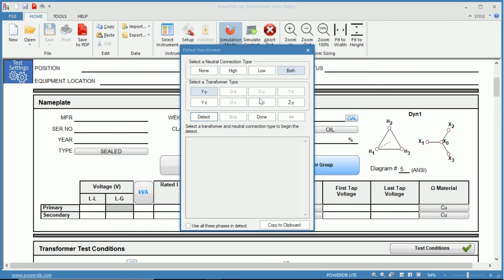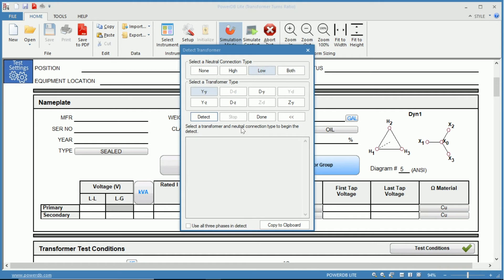In this example where we have a delta on our primary and a Y with a neutral on the secondary we would have a neutral connection only on our low side. So we know that we have a delta Y. Now you could also use this if you had a YY, a Y zigzag, a delta zigzag, or a zigzag Y.